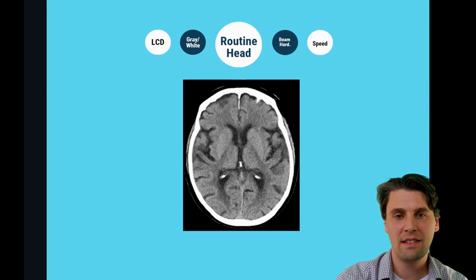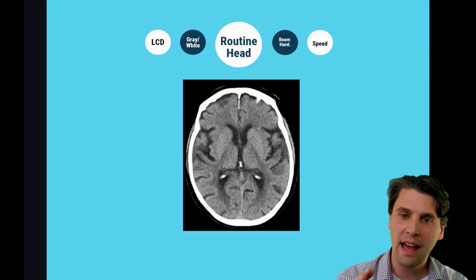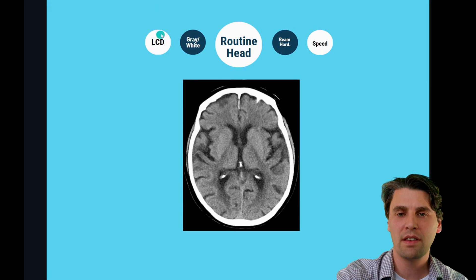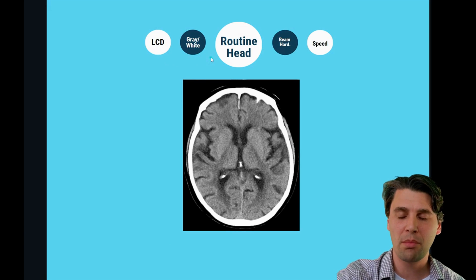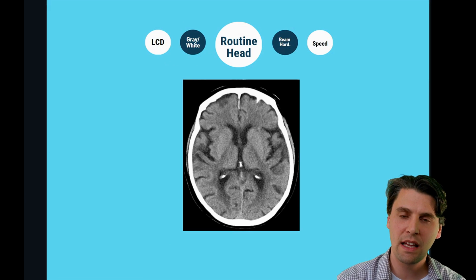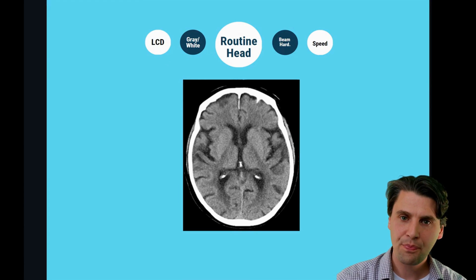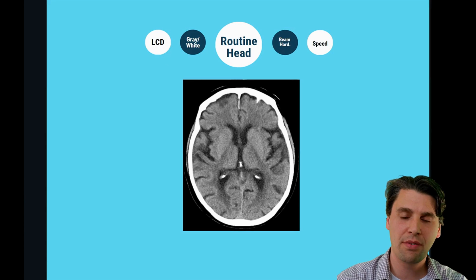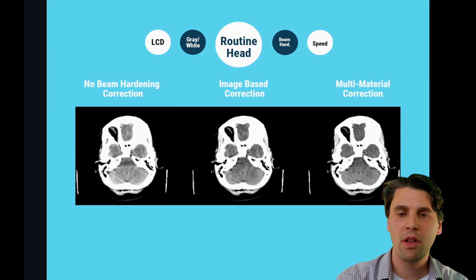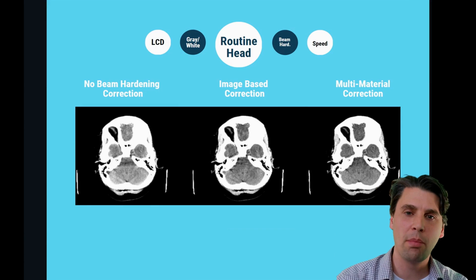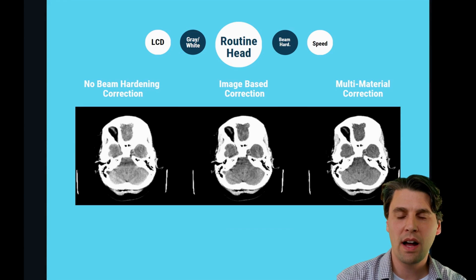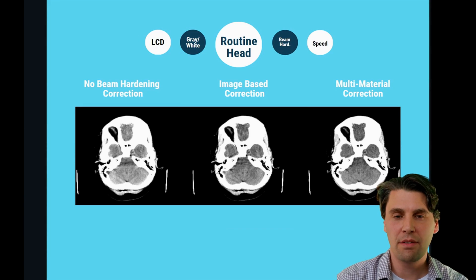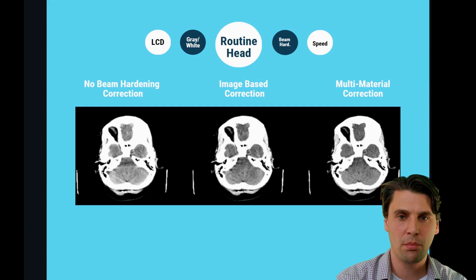First off, a routine head scan. The most important aspect there is the low contrast detectability, and the gray-white matter differentiation is really driven by how well we can differentiate low contrast objects, because gray and white matter have attenuation differences which are less than one percent. Additionally, we're talking about the thickest and most dense bone in the body. In the posterior fossa, we typically have significant beam hardening artifacts, as well as in other areas of the brain.